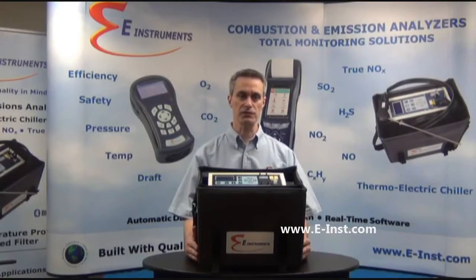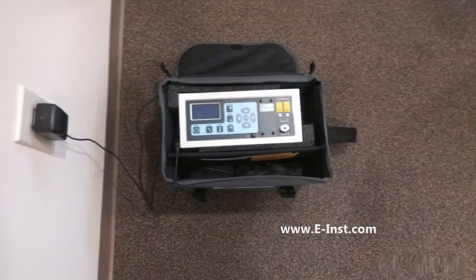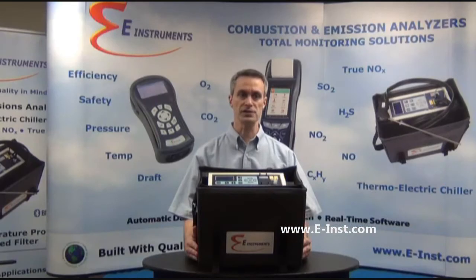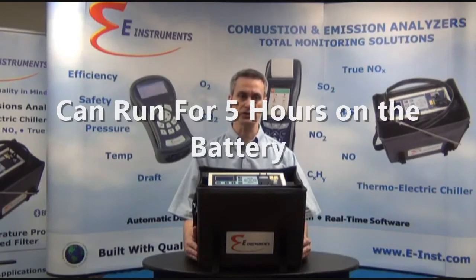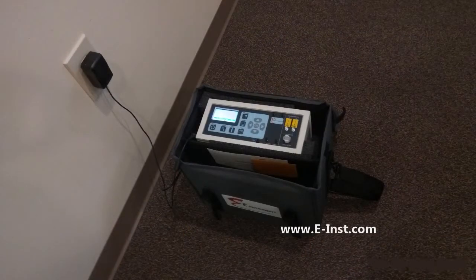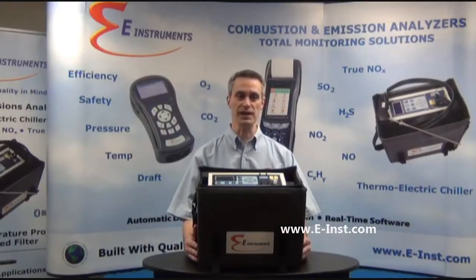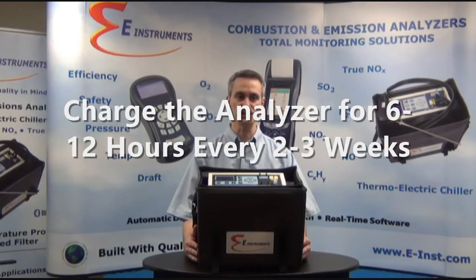The E8500 Plus can run off rechargeable battery power or AC power. If you plan to run off battery power, please make sure to charge the analyzer the entire night before with the unit turned off. The analyzer can run up to 5 hours on a fully charged battery pack. It is recommended to run off AC power as often as possible. If you do not plan to use the E8500 Plus for several weeks, then it is recommended to charge the analyzer for 6 to 12 hours every 2 to 3 weeks.